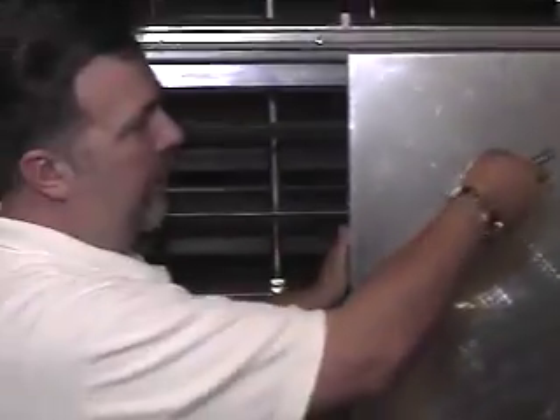Here's one of the dampers I was showing you on the graphics. So right now we're open to this side. And if we look inside here, you can see that set of dampers is shut. So we're either flowing around the coil, this is the bypass section, or inside here, you're flowing through the coil itself. So there's a set of dampers here, and then there's another set on the other side of the coil.